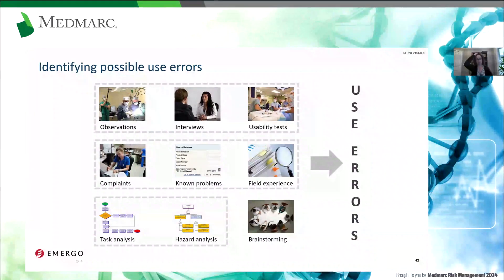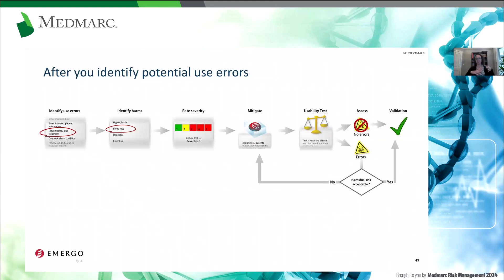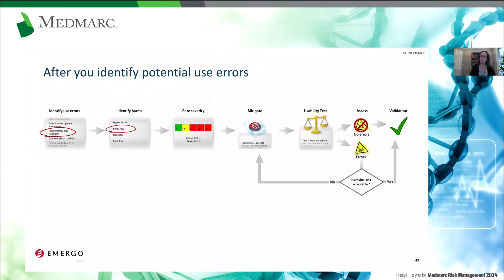You might have complaint data from post-market surveillance to reflect on, and getting together with a multidisciplinary team of individuals is also valuable for brainstorming. Basically, you're identifying errors, thinking about what harms can occur from each error, and writing the severity of harm. On a five-point scale, you might have: negligible, minor, serious, critical, and catastrophic. Then you decide — anything above a three or higher, for example, is what you're concerned about. Those items you definitely need to address. You look at how you can reduce the severity of those harms and/or the likelihood of those occurrences happening, and you build in some mitigations.